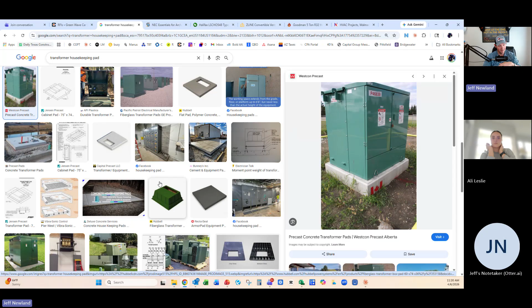That's basically what you need to think about. But the scope gap is they're very seldom called out on any of our projects, so that typically ends up being an add, because the concrete guy's never going to pick them up unless they're called out - he's not going to pay any attention to what equipment is going where. So is that something you could avoid as a PM by reviewing the plans and seeing there's a transformer out there in the yard? You're automatically going to know we need a housekeeping pad for that.